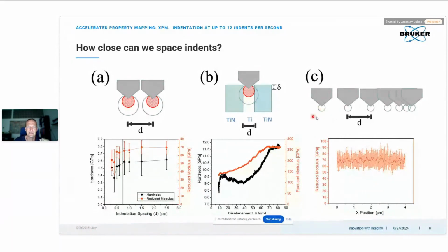And then ideally, if you're just interested in the elastic modulus, the spacing can actually be very, very small, because there is no plastic deformation left, so there is no deformation of the surface. There's supposed to be no change in the material properties after unloading, so you can actually space the indents very close to each other, so you get a flat line for the reduced modulus over the lateral positions here. So elastic modulus is actually more forgiving, let's say, if you're interested in the elastic modulus only, but hardness is a very different story, because you have to take into account the plastic deformation zone under the indenter.